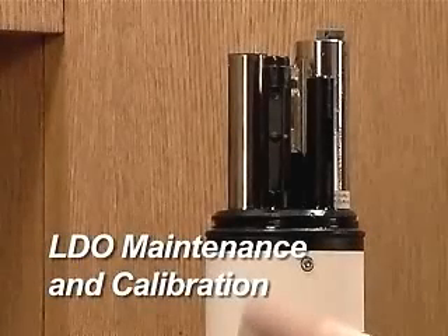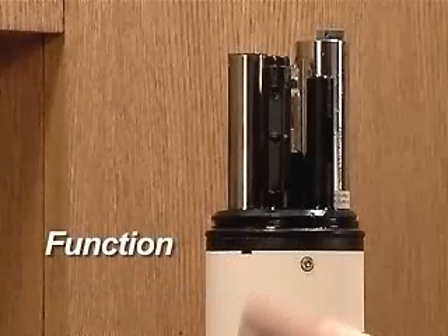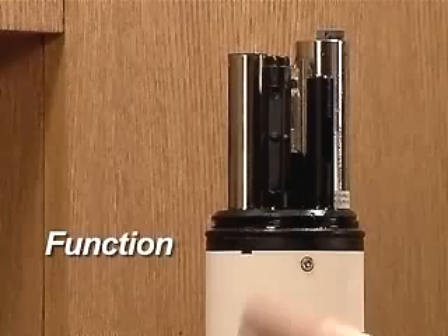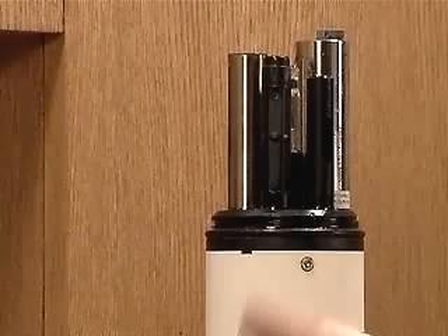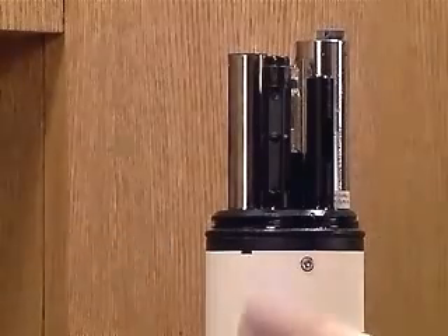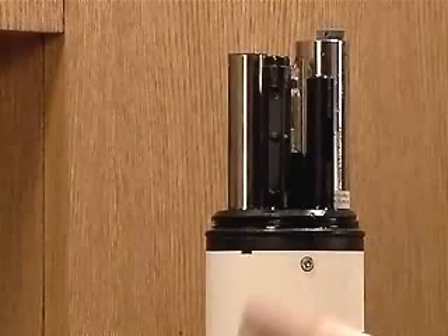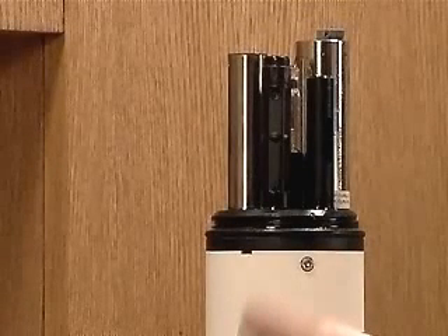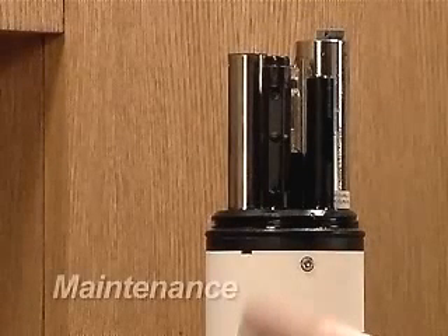LDO maintenance and calibration. Function. The Hach LDO probe measures the oxygen dissolved in water by flashing a blue light on the sensor cap, coated with a luminescent material, and measuring the time it takes for the sensor to return red light. More oxygen in the water causes a shorter time delay.